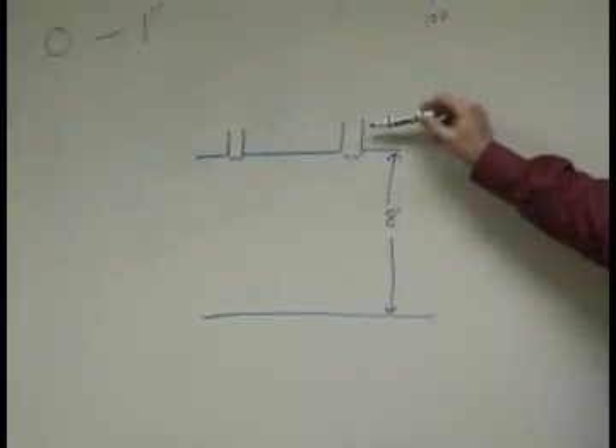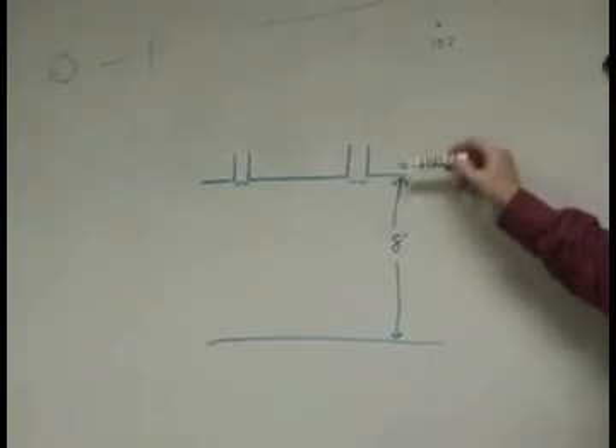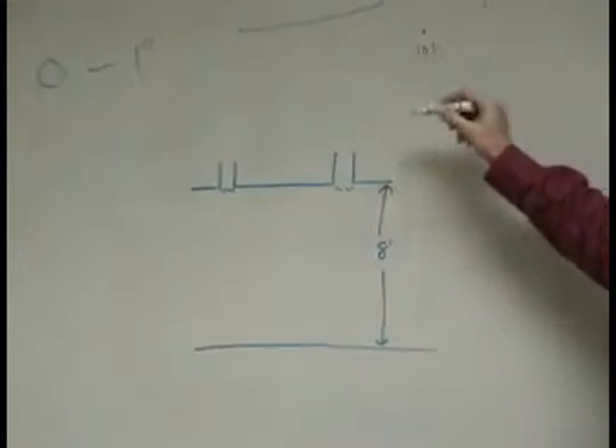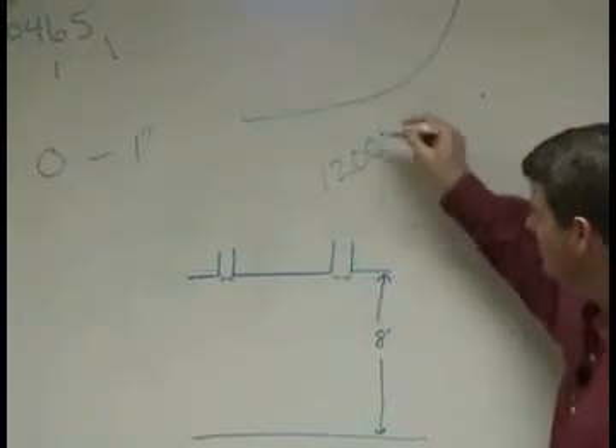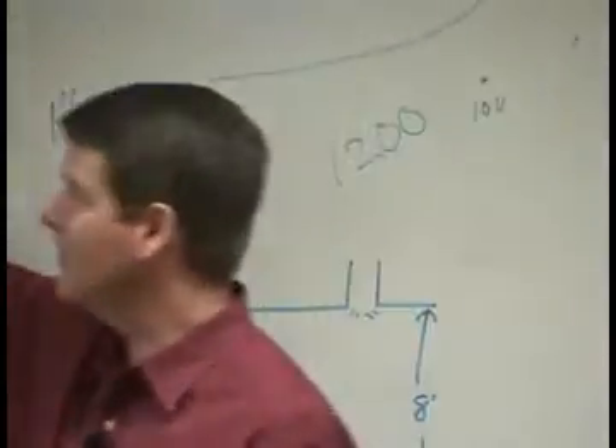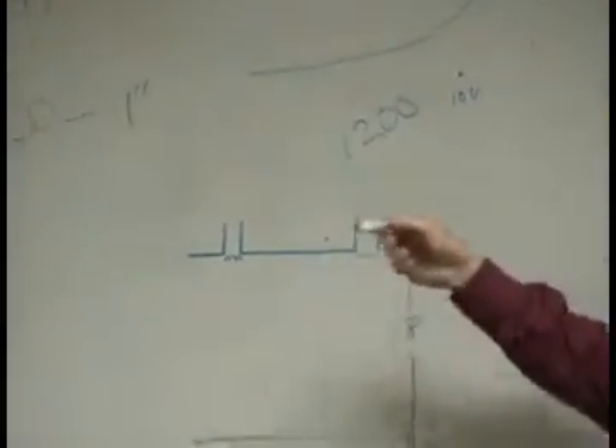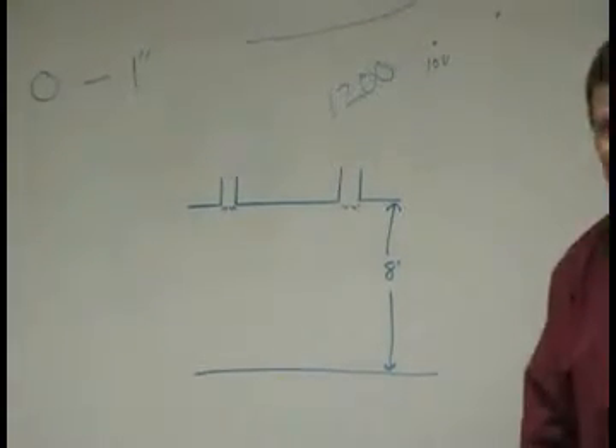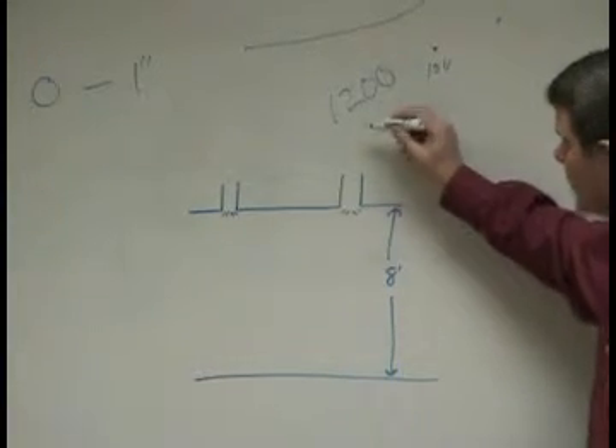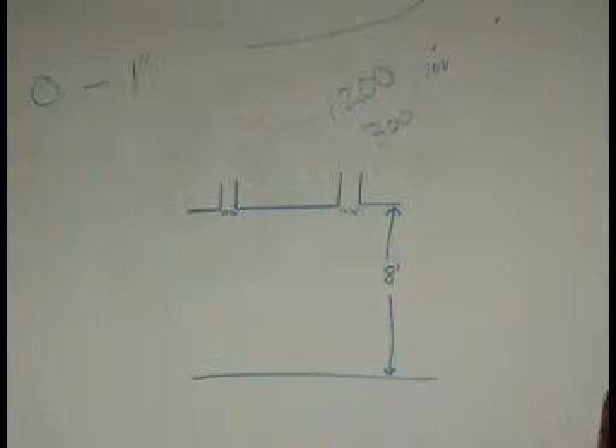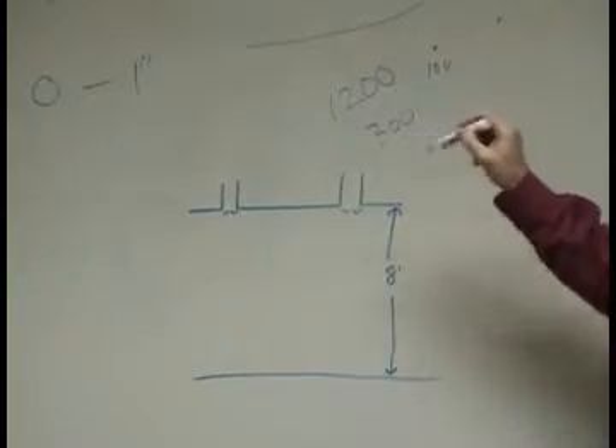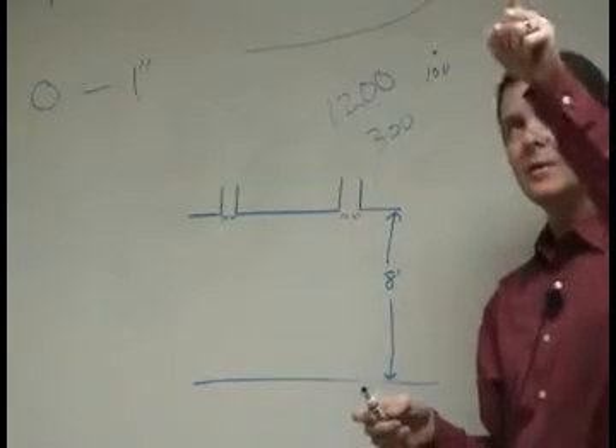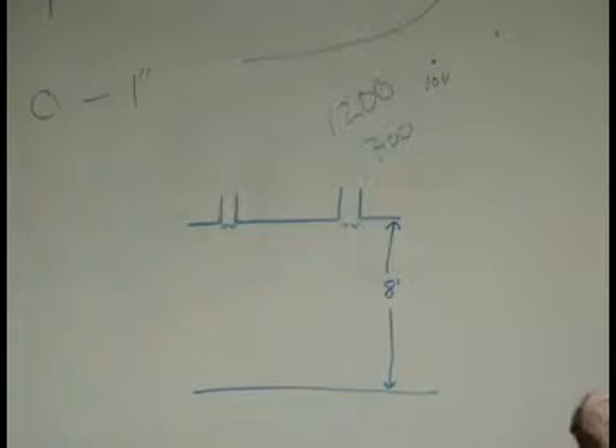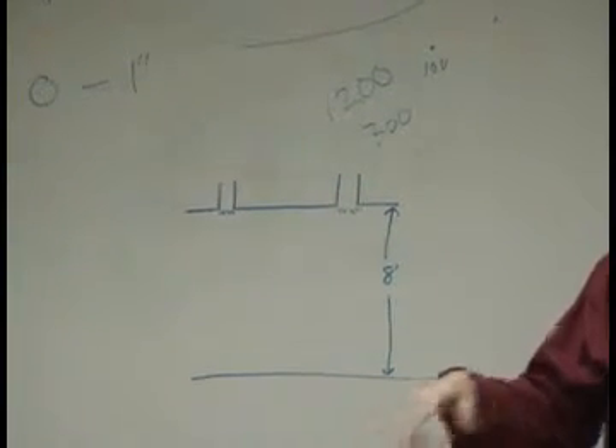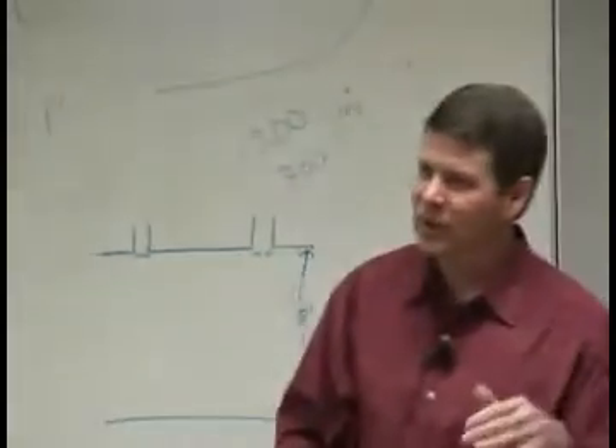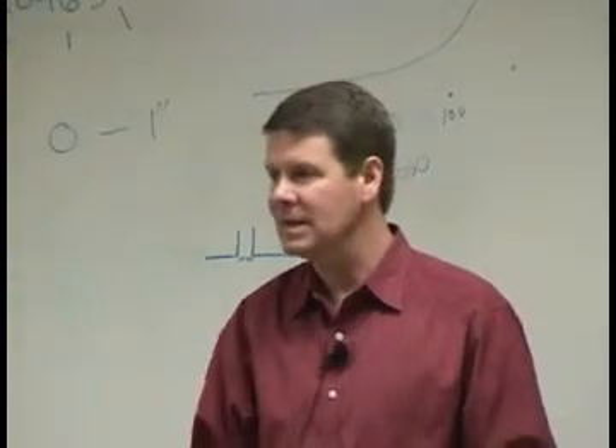Okay, here's my cross section of the room. This is a normal 8-foot or so ceiling. We've got a couple of diffusers. Let's say we started with, for easy math, 1200 CFM is our design CFM, our high end. Let's say they decided they wanted to put 4 diffusers in the room. They put 4 diffusers in, so we're going to have 300 each. Now they probably arrived at that saying to themselves, okay, when I have 300 CFM coming out of that register, I'm going to size that register so that I get throw of the register to get down near the occupants, but not necessarily blow their hair off, but get it down into the room.